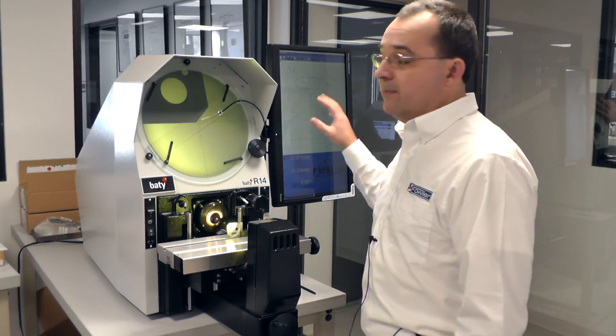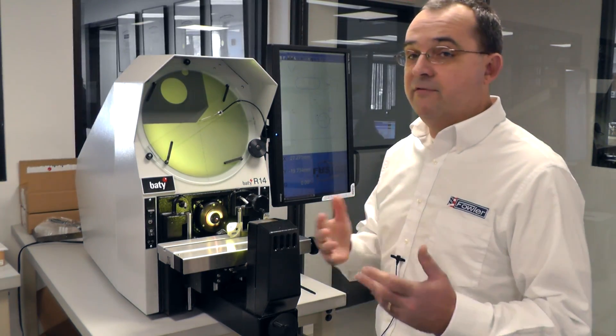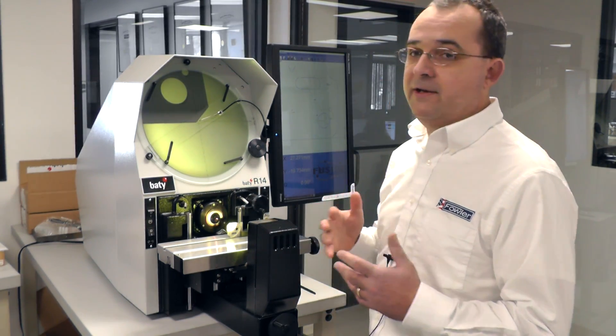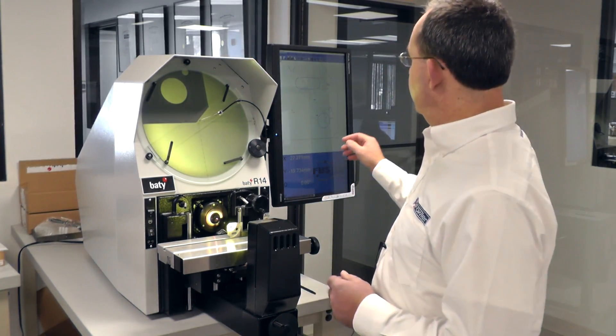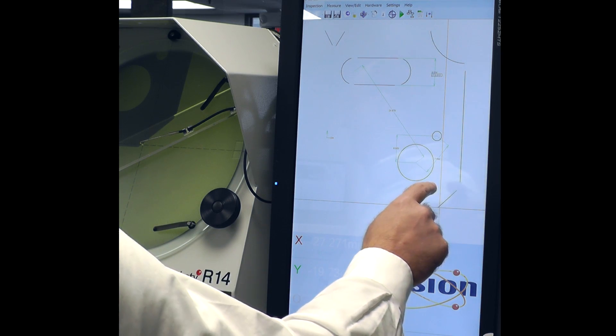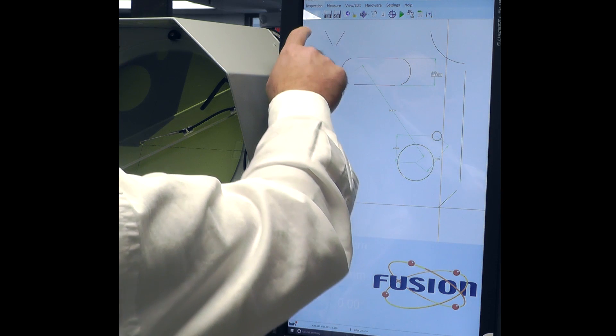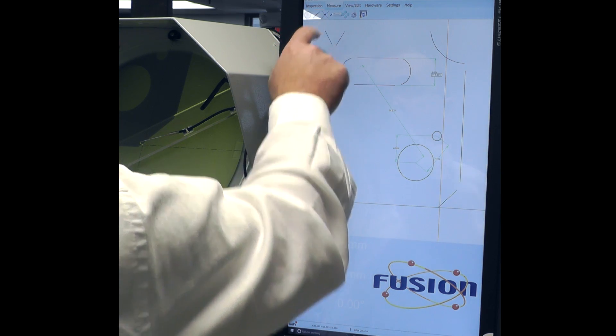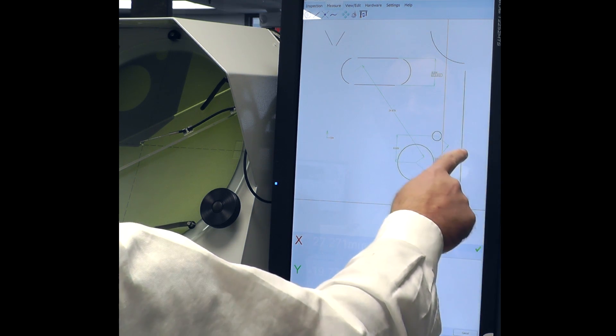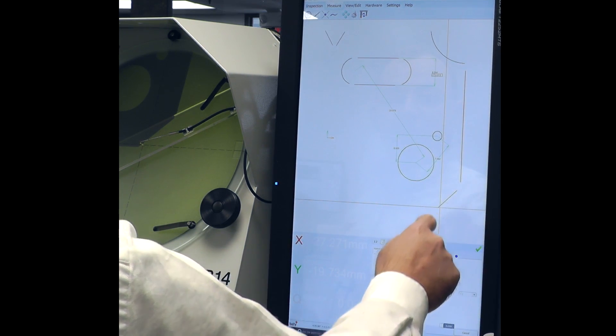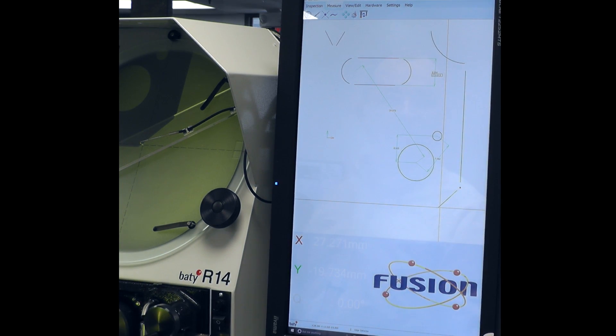One of the big advantages to this type of product is that you can construct lots of different features from previously measured features, which would be near impossible to do on a small readout that you may already have on your optical comparator. For this example, I'm going to construct a point on the intersection of these two lines that you can see right here. So I select point in my measurement routine, then select the small wrench which allows me to enter features to construct that point from. And as you can see, I have a point there. I say finish — I've done that point.